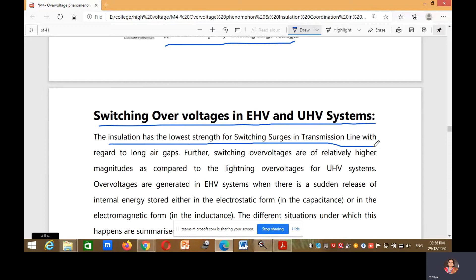Next is the switching overvoltages in extra high voltage and ultra high voltage systems. The insulation has the lowest strength for switching surges with regard to long air gaps. Switching overvoltages are of relatively higher magnitude as compared to the lightning overvoltages for ultra-high voltage systems. Overvoltages are generated in extra high voltage systems when there is a sudden release of internal energy stored either in the electrostatic form or in the electromagnetic form.